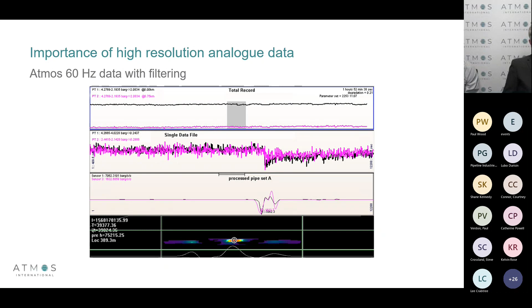Another example we've got, and this is a genuine leak detected on a water pipeline in the UK. What we've got here on the left is the data provided by the customer, where they were collecting data every 15 minutes. This pressure drop represents the same pressure change we've got here, and this was an air valve failing. When the pipeline was shut down over a long period of time, the pressure slowly started to fall away at quite a significant rate, and it triggered a low pressure alarm.